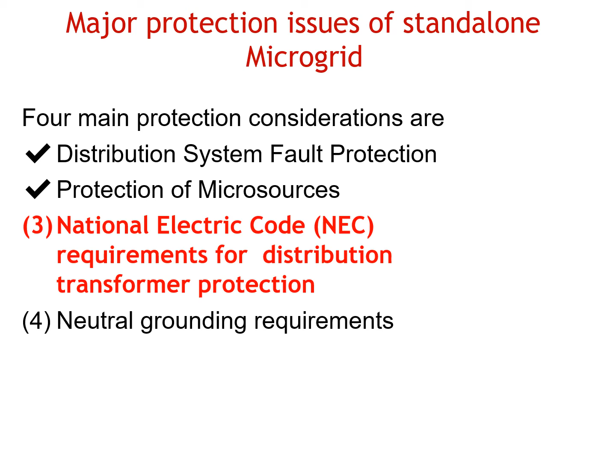Let's see the third protection issue of standalone microgrid, that is National Electric Code requirements for distribution transformer protection. So prior to designing a protection scheme for this medium voltage or low voltage distribution transformer, careful assessment must be carried out to check whether this overcurrent protection requirement of the NEC for transformers suits much lower fault current capacity microgrid networks. About 600% of the transformer rating, that is Article 450 of the NEC.